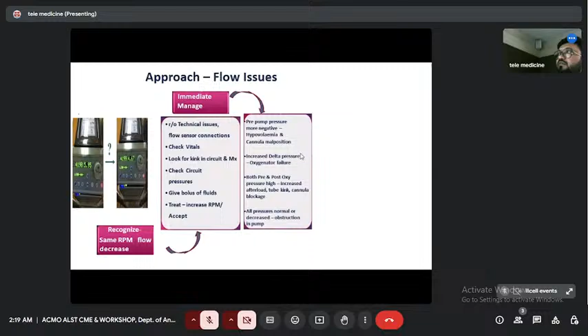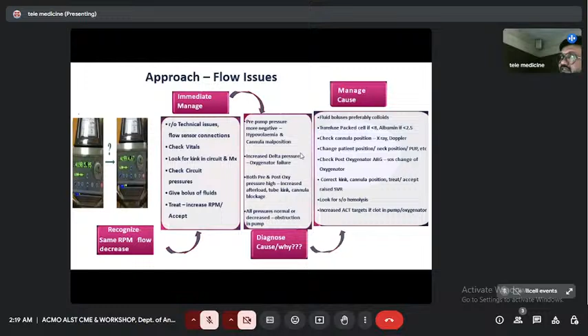So I think if it is hypovolemia, give fluid boluses, mostly colloids, and check the cannula position with the help of X-ray or Doppler and reposition accordingly. And keep the neck position neutral and limb position normal. And check the post-oxygenator ABG. If there is any change, the post-oxygenator ABG will show low oxygen, and also change the oxygenator. And see for the signs of hemolysis. If that is there, increase the ACT values. ACT value should be on the higher side.